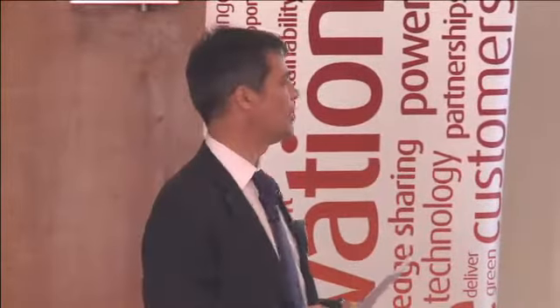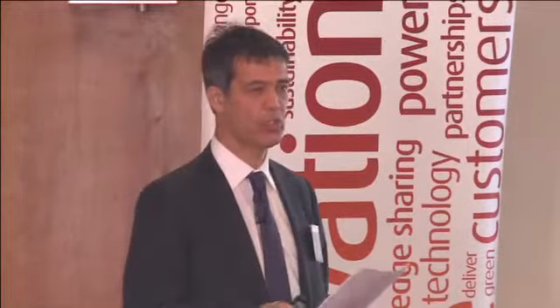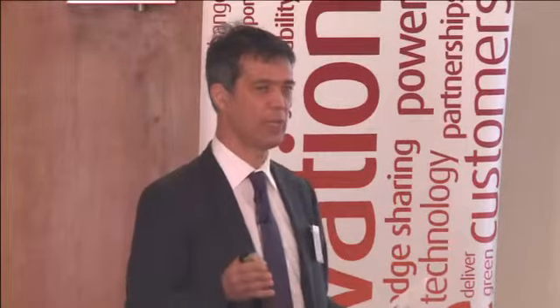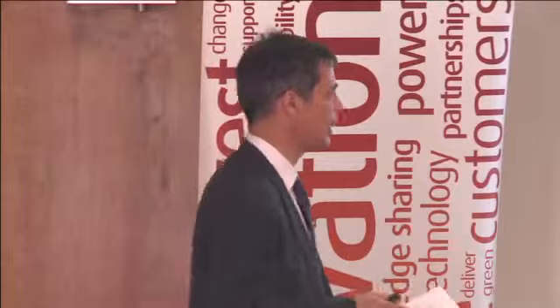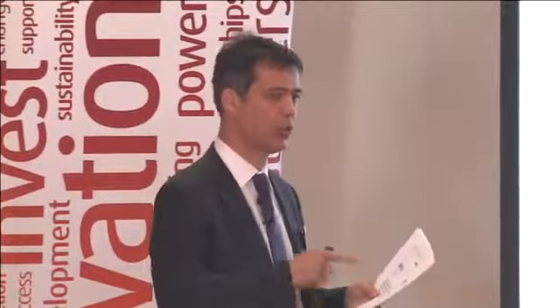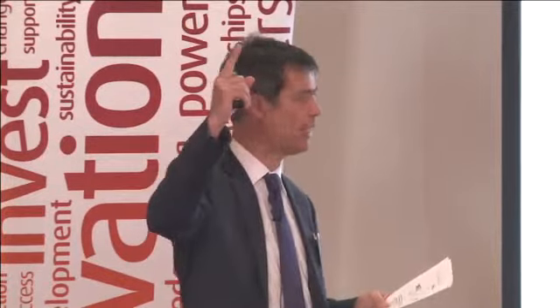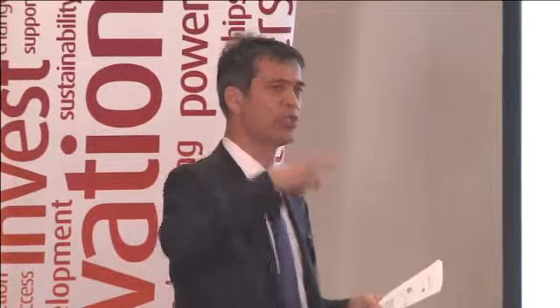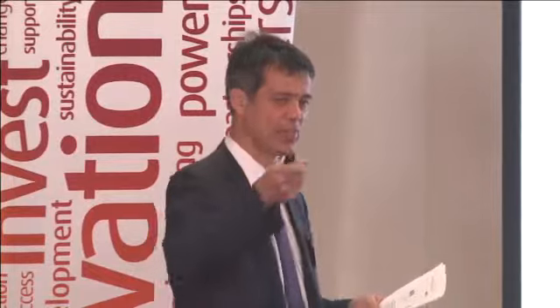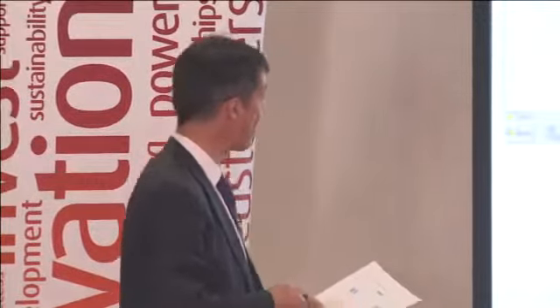Finally, we've got another device called a field service unit, which connects via USB into an operator's laptop. When the guys are deploying equipment, or want to go out and do investigations into the network, they can use that to talk to the devices. So, for example, if you've got a relay that's 7 meters up in the air, you can talk to it by radio without having to physically connect into it.